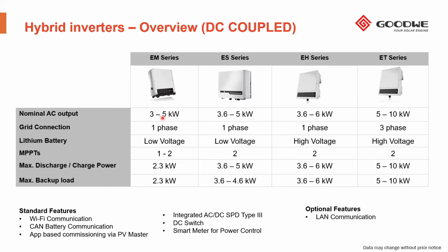So a 3 kilowatt EM inverter will have 1 MPPT, whereas a 5 kilowatt EM inverter will have 2 MPPTs. So just be aware of that. Just look on the data sheets, as always a good reference in case you need any additional information. In terms of the maximum discharge and charge power, regardless of the size of the inverter, they are capped at 2.3 kilowatts. And the maximum backup load that you can connect to this inverter is 2.3 kilowatts.